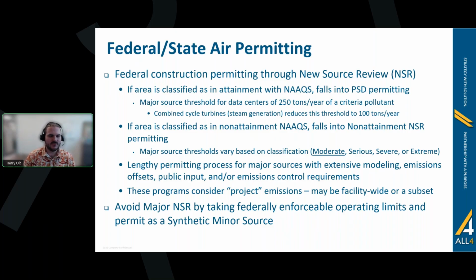The major source threshold for PSD's 28 identified source categories is lower, but data centers typically don't fall into any of those sources. Should your site have on-site power generation, including combined cycle natural gas turbines, the major source threshold reduces from 250 tons per year to 100 tons per year of any criteria pollutant.